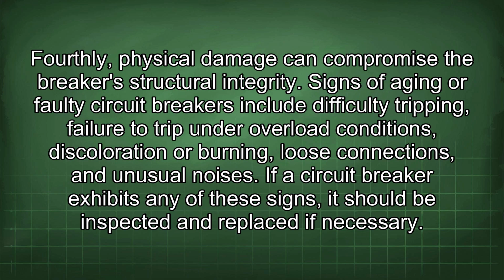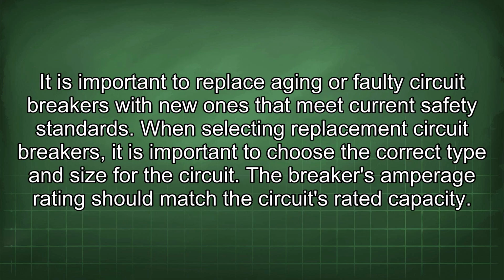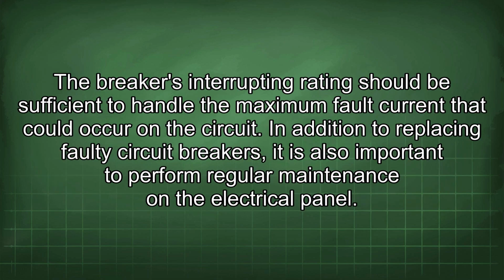Signs of aging or faulty circuit breakers include difficulty tripping, failure to trip under overload conditions, discoloration or burning, loose connections, and unusual noises. If a circuit breaker exhibits any of these signs, it should be inspected and replaced if necessary. It is important to replace aging or faulty circuit breakers with new ones that meet current safety standards. When selecting replacement circuit breakers, it is important to choose the correct type and size for the circuit. The breaker's amperage rating should match the circuit's rated capacity. The breaker's interrupting rating should be sufficient to handle the maximum fault current that could occur on the circuit.